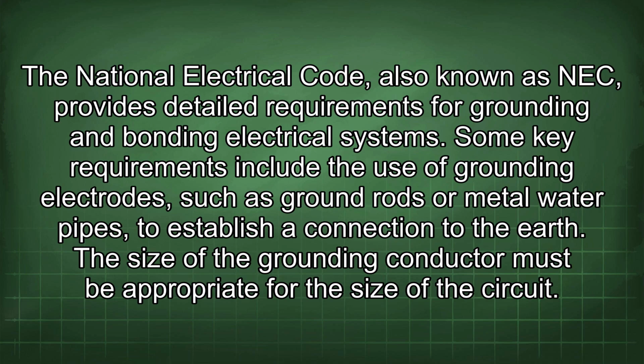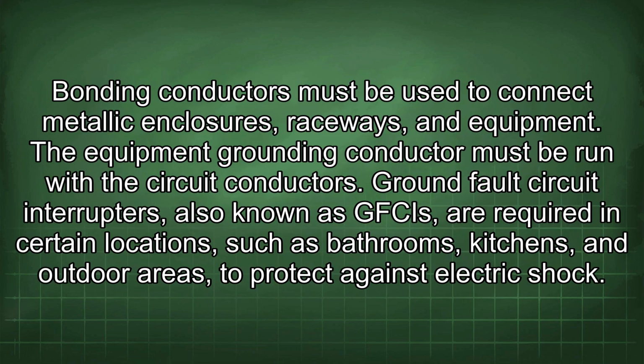The National Electrical Code, also known as NEC, provides detailed requirements for grounding and bonding electrical systems. Some key requirements include the use of grounding electrodes, such as ground rods or metal water pipes, to establish a connection to the earth. The size of the grounding conductor must be appropriate for the size of the circuit. Bonding conductors must be used to connect metallic enclosures, raceways, and equipment. The equipment grounding conductor must be run with the circuit conductors.